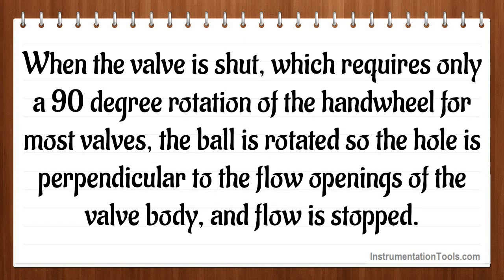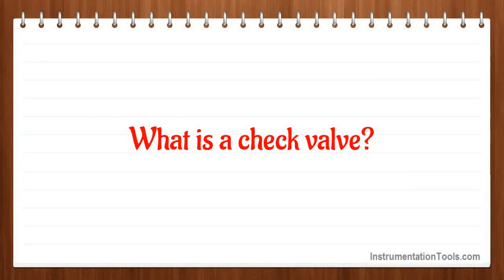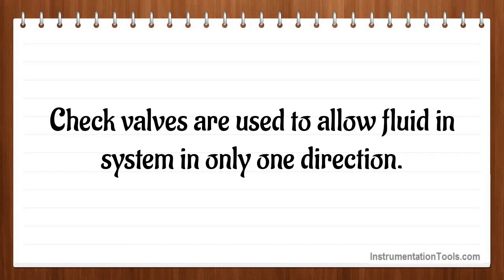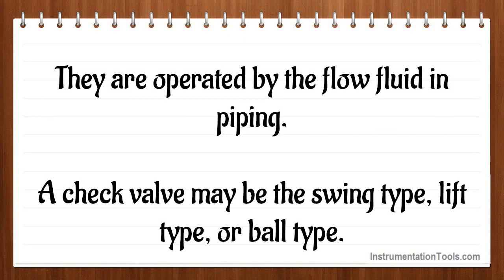When the valve is shut, which requires only a 90-degree rotation of the handwheel for most valves, the ball is rotated so the hole is perpendicular to the flow openings of the valve body and flow is stopped. What is a check valve? Check valves are used to allow fluid in a system in only one direction. They are operated by the flow of fluid in piping. A check valve may be the swing type, lift type, or ball type.